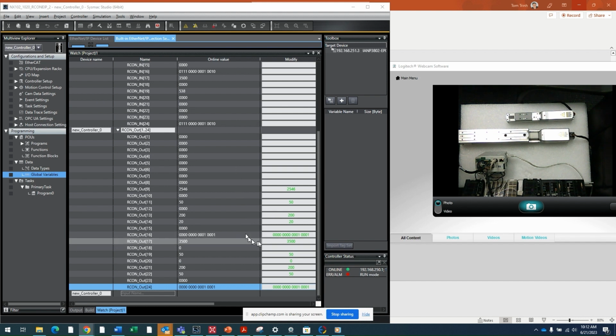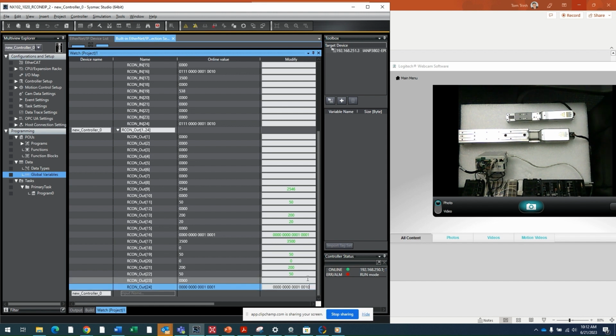All right, on this side, if you look here at the bottom, the RCON out 24, these are the control bits. So I can turn on my servo as well as execute the position. Right now, the servo is already on, which is bit number 0, 1, 2, 3, 4. Bit 4 is on, okay? And I'm going to go ahead and tell it to go home, which is bit 1, which is this bit right here.